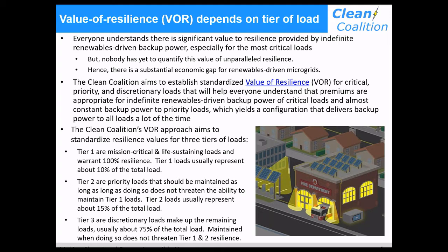Tier 1 are the most valuable loads - mission critical, life sustaining loads - and they should have 100% resilience. Tier 1 loads in a typical facility represent about 10% of the total load.